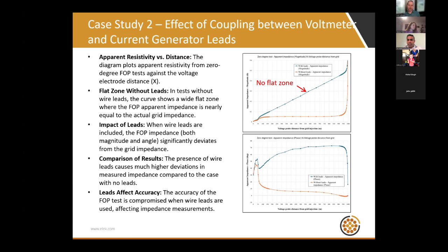So the first part of the test or the simulation, we ran the voltage measurement leads in the same direction as the current leads. And we can see in the top right-hand corner this plot here. The orange plot is without leads, and the blue plot is with leads. And we can see a really high distortion of the apparent impedance that's been measured.